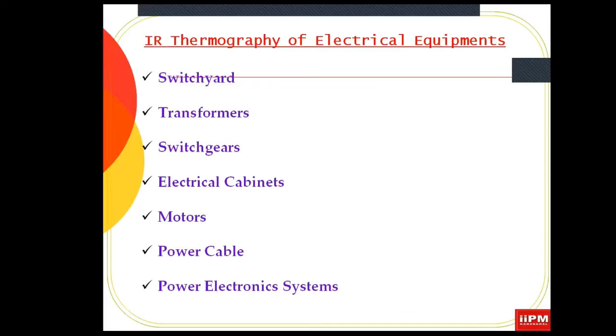Normally in electrical equipment, we are using switchyard, transformer, switchgear, electrical cabinets, motors, power cables, and power electronics. What problems can we find? Due to temperature rise as current flows, a loose joint, or deposition of contaminated, oily substance, looseness, a hotspot will be detected. It can cause open circuit, maybe short circuit, and fire hazard. From the fire hazard, we can save the transformer. The transformer is the heart of the power center, and in the transmission line and the substation, we mostly use the thermography camera. So that can help you a lot.